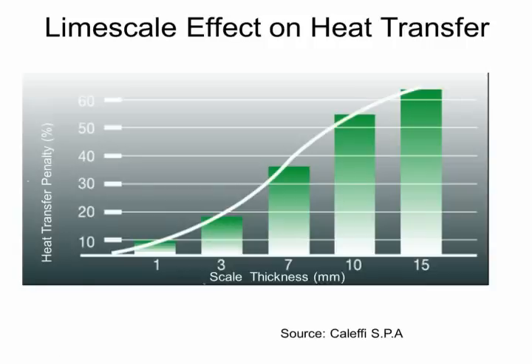Now, some designers might say, I don't mind a little bit of limescale, because once it precipitates out of water and onto the metals inside of the system, it protects them from further corrosion, perhaps from galvanic attack or even chemical corrosion from air. Well, that doesn't really hold true, because one of the things about limescale is it really is affected by temperature. So perhaps those iron pipes that you're looking to protect from corrosion somewhere down in time, they don't really scale up.